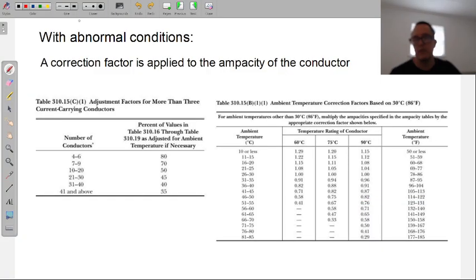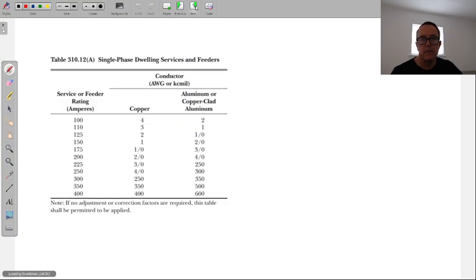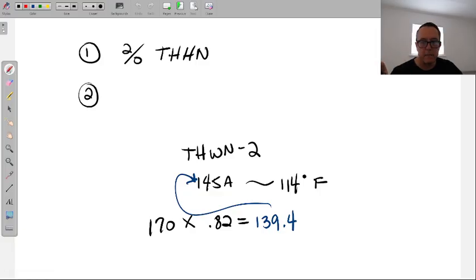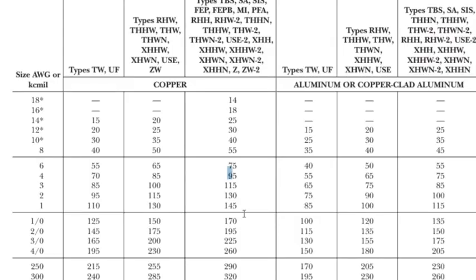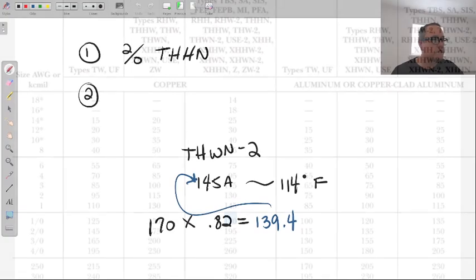Here's where we iron out those details. There was another question that came up, or was trying to come up, I think. Where did that 170 come from? Say that again? Oh, 170? The 170 came from me just selecting the next size higher than 145. It's coming over here and going, all right, 145 it won't be. The number 1 it can't be because I'm going to reduce this. So I'm just going to that next size higher, making a decision here to go to the next one.